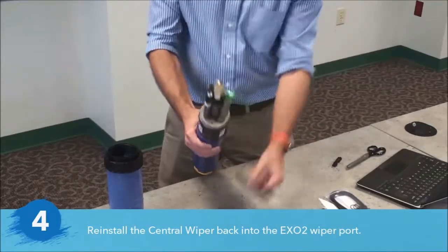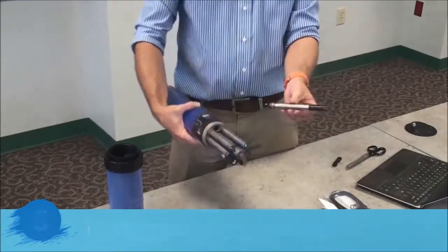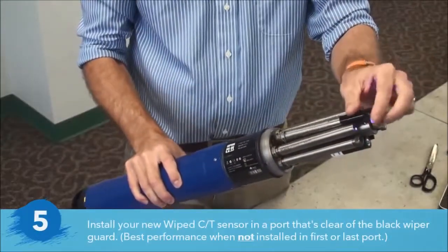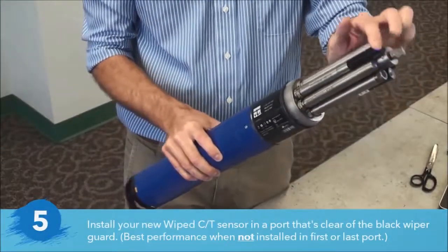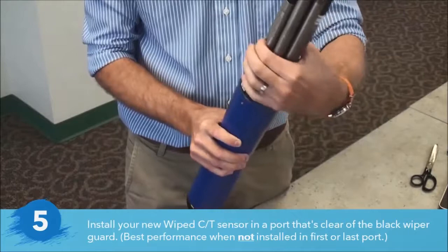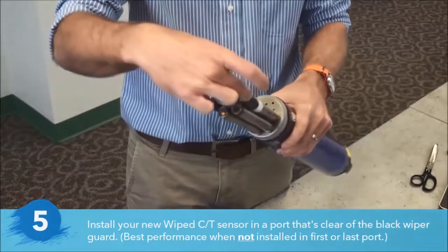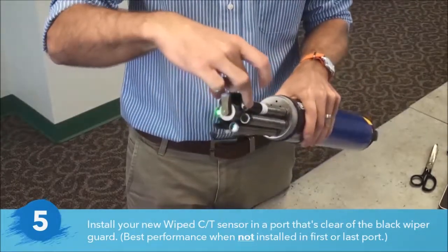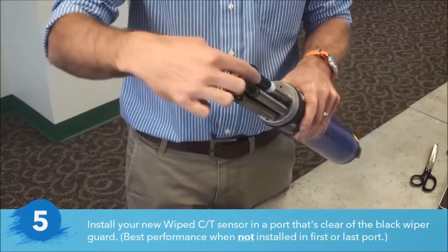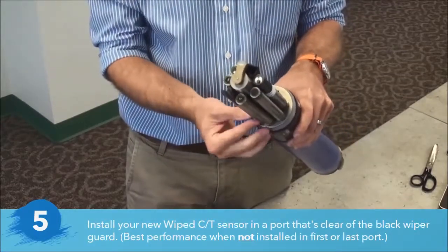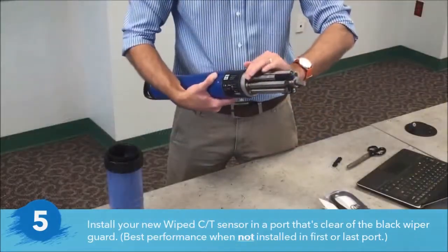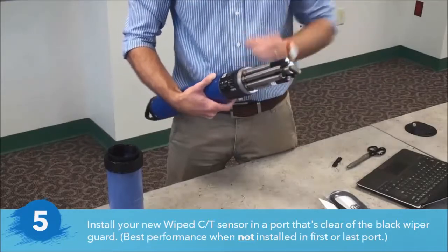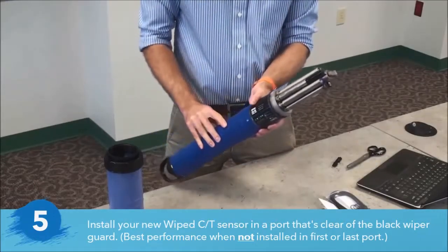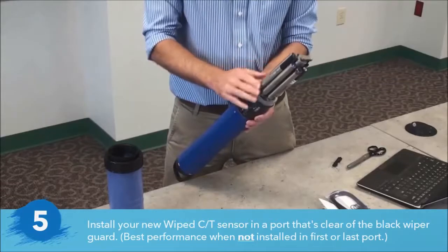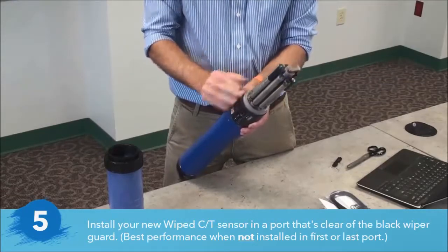The next step is to take the wiped conductivity probe and install it in a port away from the wiper guard. So having it not be the first port or last port will give you the most optimal wiping performance. Because EXOs are smart sensors, they can be installed and will function in any port. Note that your sonde code doesn't need to be updated. It will automatically work with the brand new wiped CT probe.